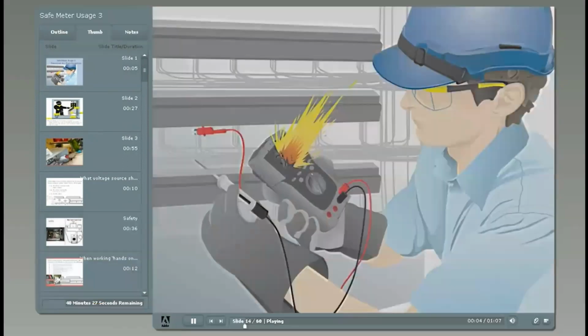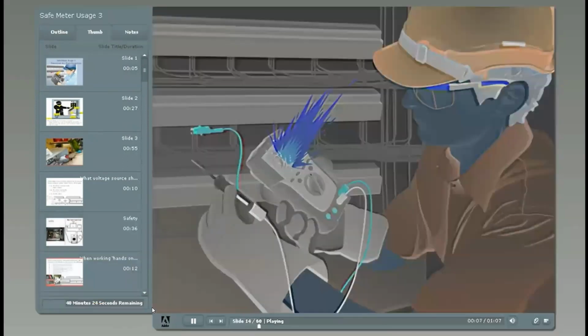Leads, which are still connected to the current terminals on the meter, to the voltage buses, a direct short across the source. If you have this thing in ohms, or if you have this in amps, and you're going across right there, it catches you by surprise. Typically, your safest thing to be doing is using your meter for the voltmeter and punching around. When you go into the ohm meter, you've got to put on your thinking cap.